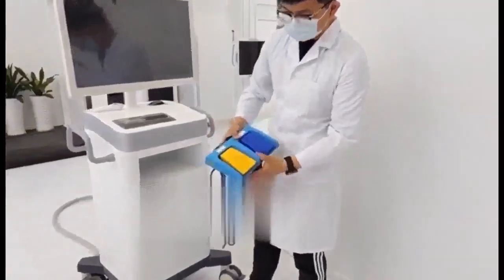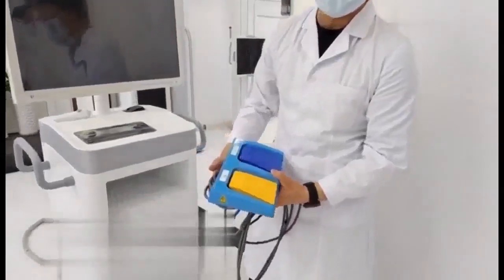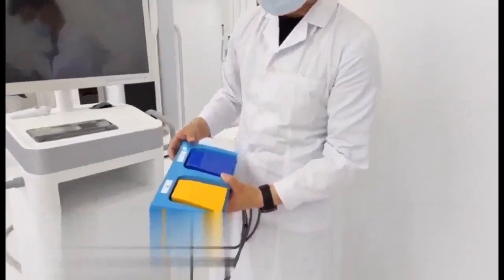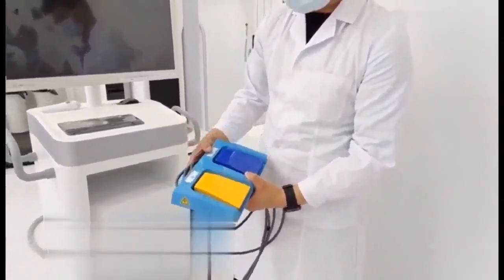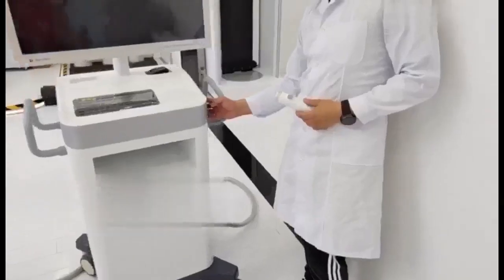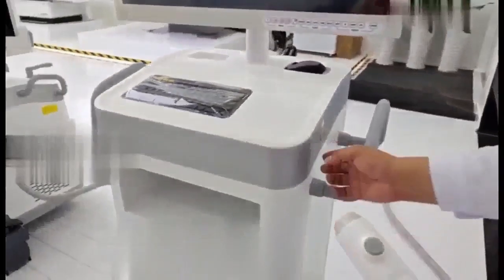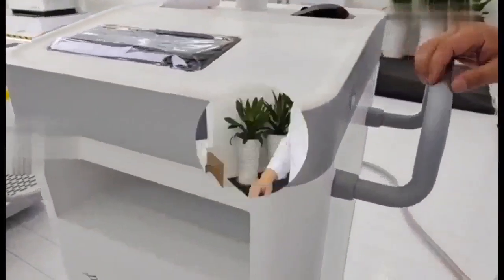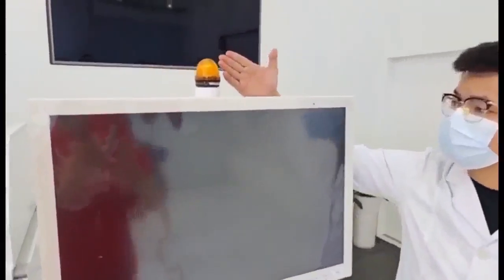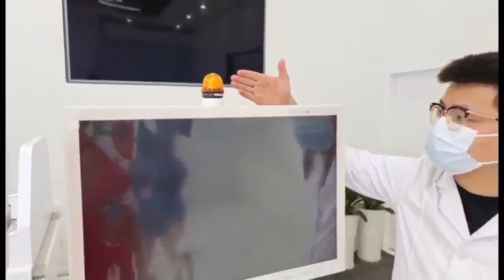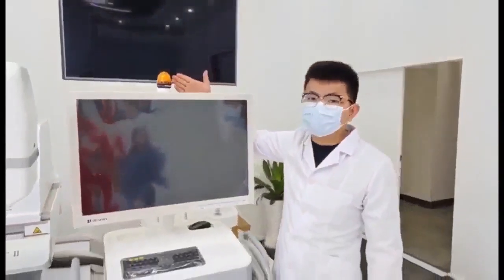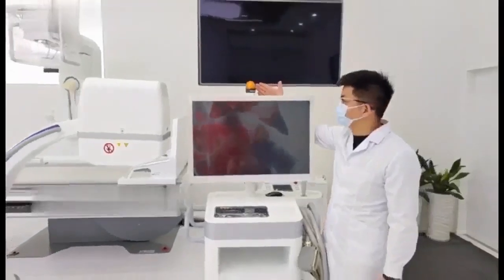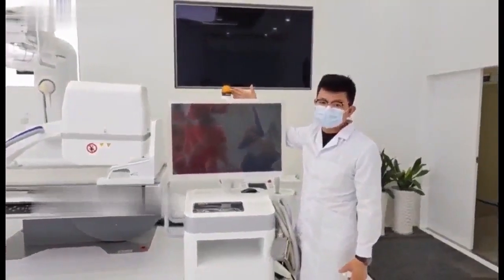And we also have a foot pedal to do the fluoroscopy or the spot film, because doctors wear surgical gowns and surgical gloves, so it's hard to handle the hand switch, and we use this foot pedal. Yellow is for fluoroscopy, and the other for film. When you press the foot pedal or hand switch, please wait until this exposure indicator light is on. If the light is not on, please keep pressing. When the light is on, it means exposure is done, and you can release your hand or your foot. You can choose the different images to be printed.